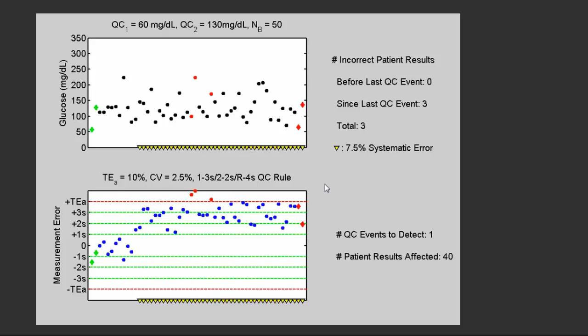We find that over 80% of the time, we wouldn't expect any QC results to be unacceptable prior to the last good QC event. This is due to the fact that in over 80% of the cases, we're detecting the out-of-control condition at the next scheduled QC after the out-of-control condition occurs. There are none that are prior.